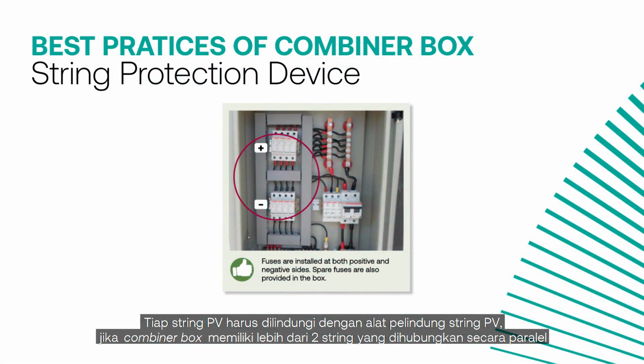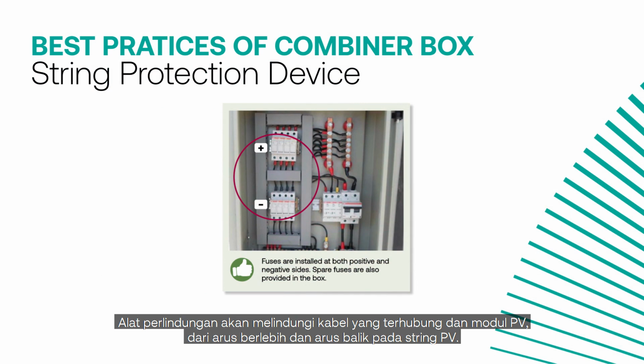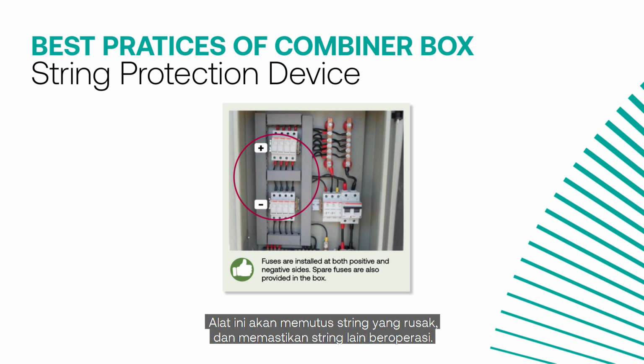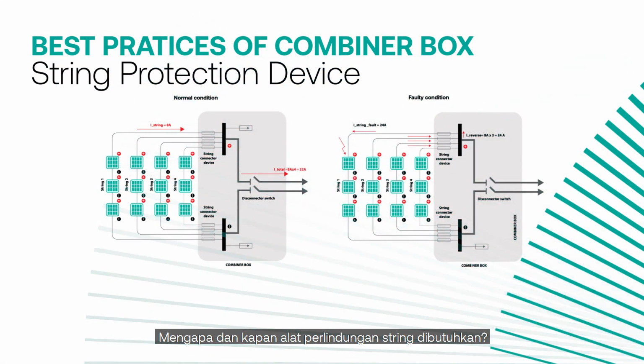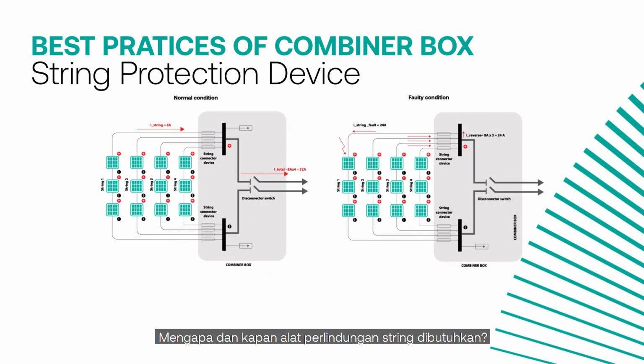Each PV string must be protected with a string protection device if a combiner box has more than 2 strings connected in parallel. The protection device will protect the connected cables and PV modules against overcurrent and reverse current in PV strings. This device will disconnect the faulty string and keep the rest of the strings in operation. Why and when is a string protection device needed?